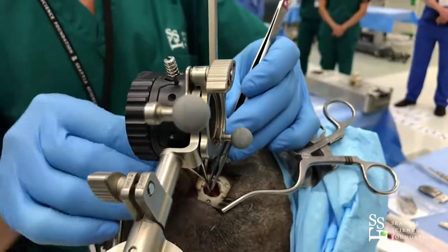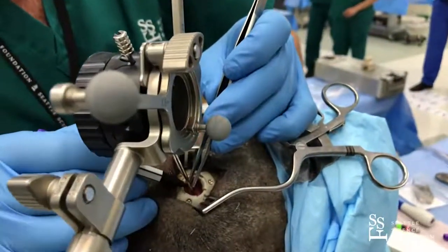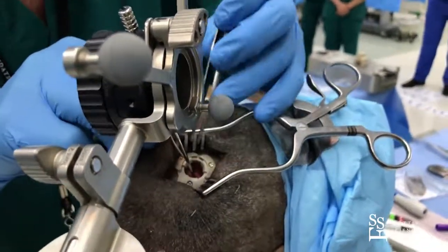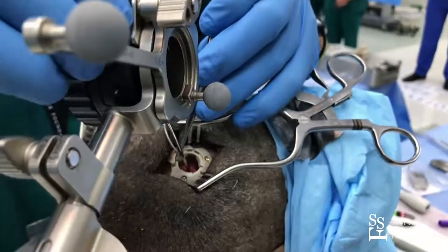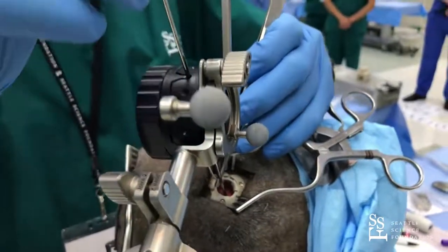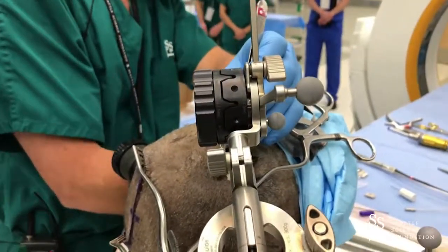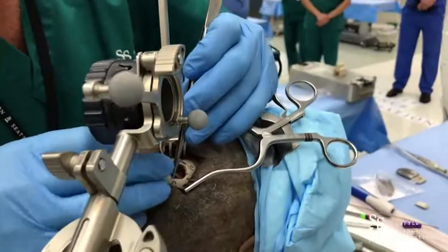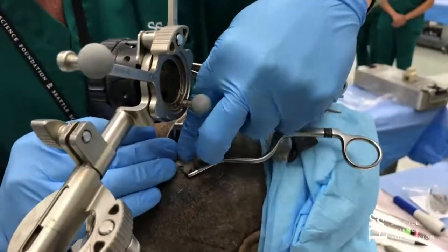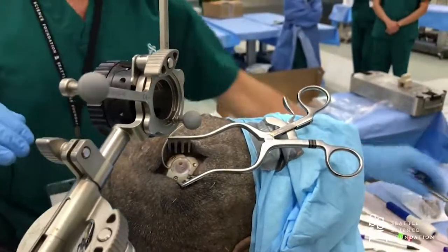And then generally, this is kind of a two-person job. You have somebody holding it while the other person is marking the electrode right at the entry point. Then you have one person holding the electrode into place while you're pulling the slotted cannula out. Okay, and you want to watch that mark that you've made so that you don't have it move in or out at all. And then you can fold it over, just like you do with the Medtronic cap or the Abbott cap, and then there's a locking piece right there. And once that's in, you're pretty safe.